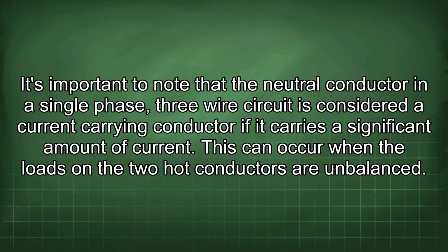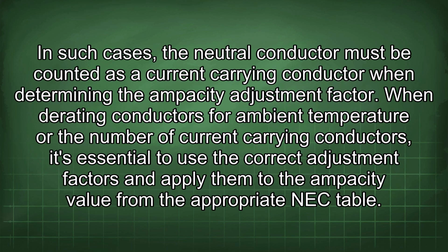It's important to note that the neutral conductor in a single-phase, 3-wire circuit is considered a current-carrying conductor if it carries a significant amount of current. This can occur when the loads on the two hot conductors are unbalanced. In such cases, the neutral conductor must be counted as a current-carrying conductor when determining the ampacity adjustment factor.